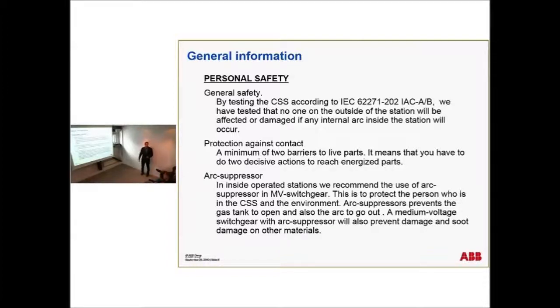We have tested according to IEC 62271-202, internal arc classification A and B. That means 2 tests, 21 kiloamps for 1 second. I'm going to show you that a little bit later on the slides, but we have done the testing and filmed with a high-speed camera what happened with the substation.